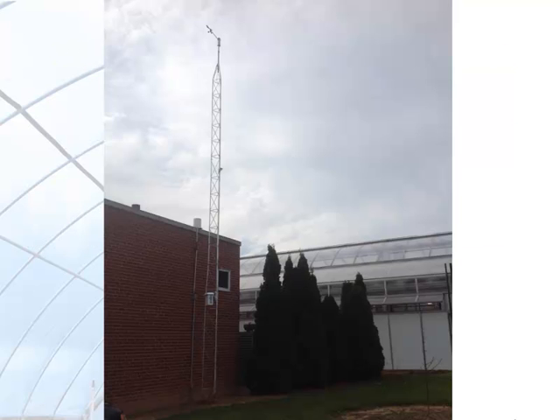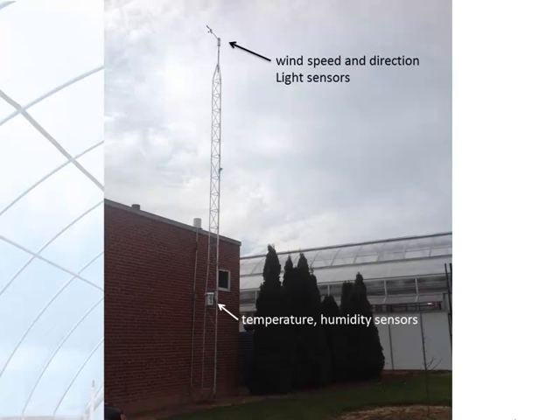How about the weather station installation in this picture? Here we see the wind speed, wind direction, and light sensor are all mounted on top of the tower with sufficient clearance from the building below. Next are a temperature and a relative humidity sensor mounted in an aspirated radiation shield. Take 5 seconds. Look closely to see if there is something that may need improvement.